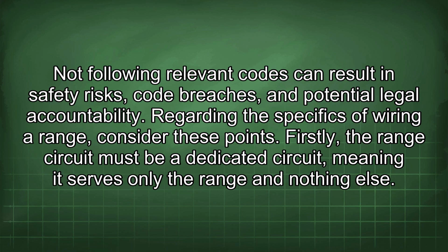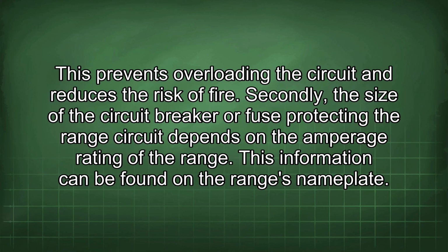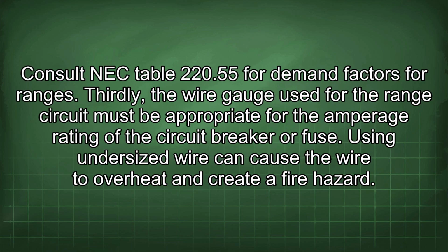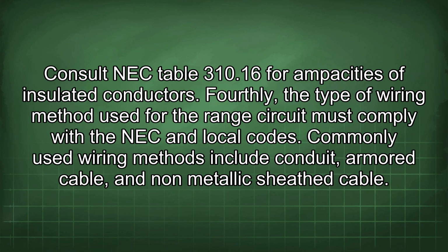Regarding the specifics of wiring a range, consider these points. Firstly, the range circuit must be a dedicated circuit, meaning it serves only the range and nothing else. This prevents overloading the circuit and reduces the risk of fire. Secondly, the size of the circuit breaker or fuse protecting the range circuit depends on the amperage rating of the range. This information can be found on the range's nameplate. Consult NEC Table 220.55 for demand factors for ranges. Thirdly, the wire gauge used for the range circuit must be appropriate for the amperage rating of the circuit breaker or fuse. Using undersized wire can cause the wire to overheat and create a fire hazard. Consult NEC Table 310.16 for ampacities of insulated conductors.